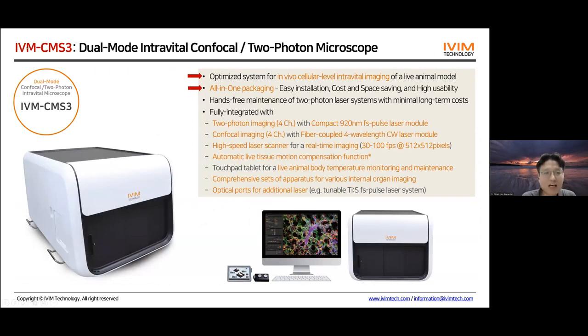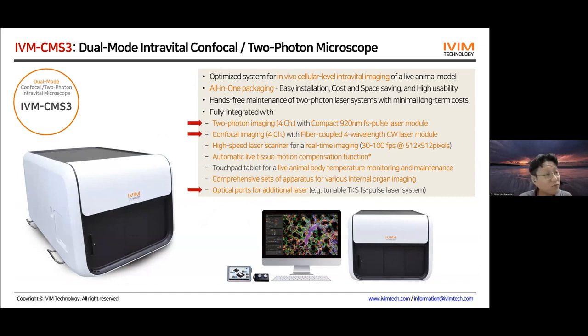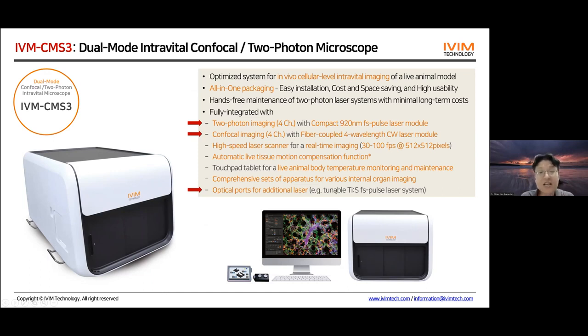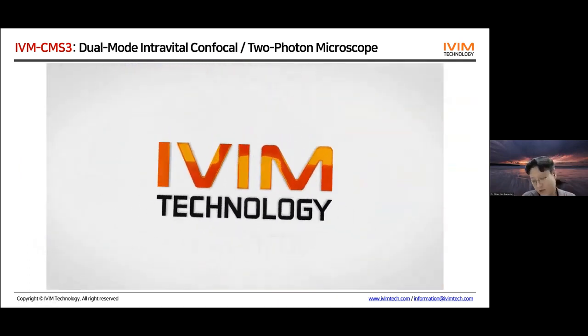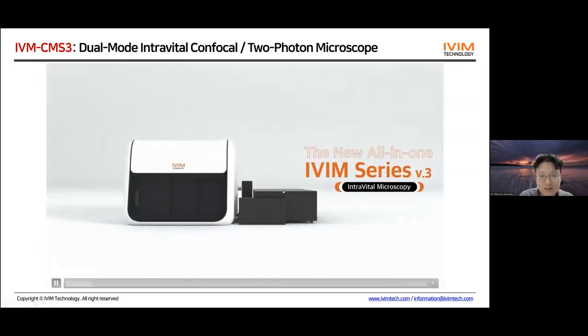Let me briefly introduce our dual-mode intravital confocal and two-photon microscope, the IVIM CMS3. It is a single-box, all-in-one system optimized for in vivo cellular-level imaging in live animal models. It can perform two-photon imaging with four different colors using a compact femtosecond pulse laser integrated inside the box. Simultaneously, it performs confocal imaging with four colors using four-wavelength confocal laser modules, and also has additional optical ports to connect external tunable Ti:Sapphire femtosecond laser systems.